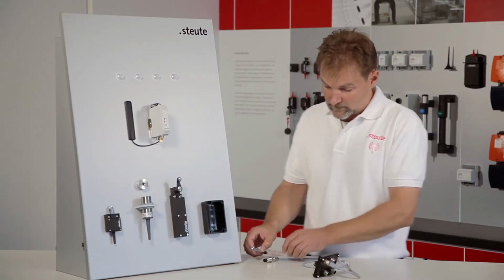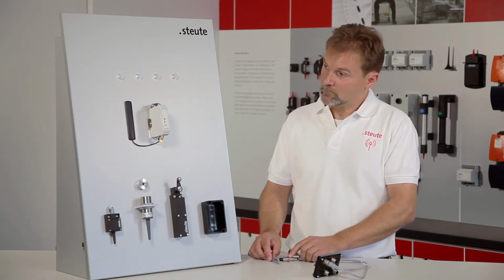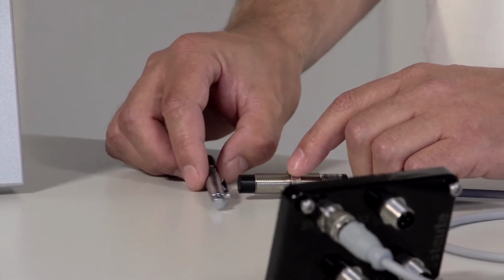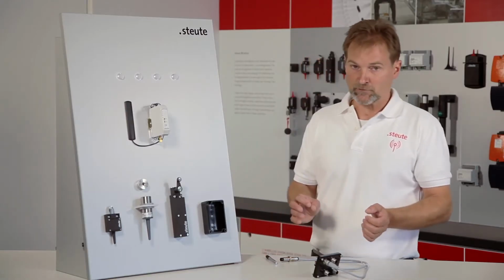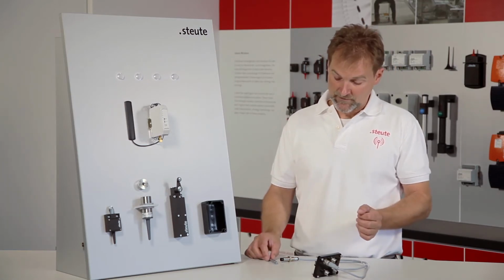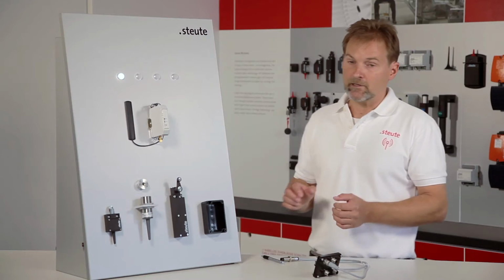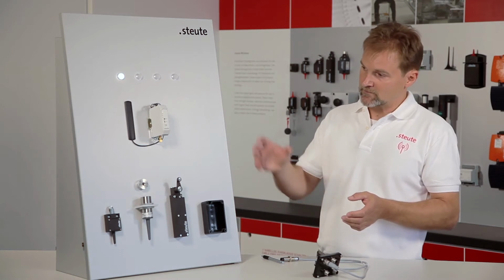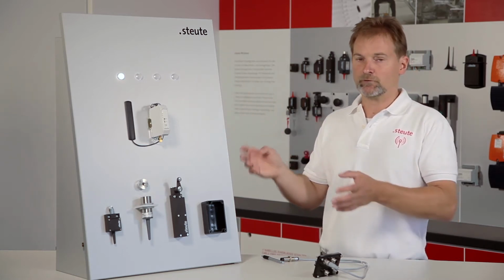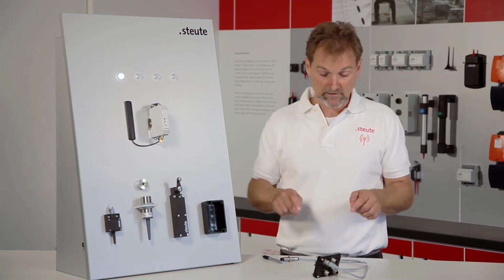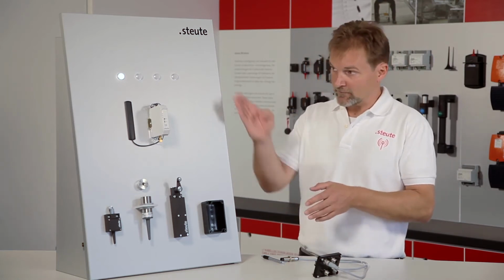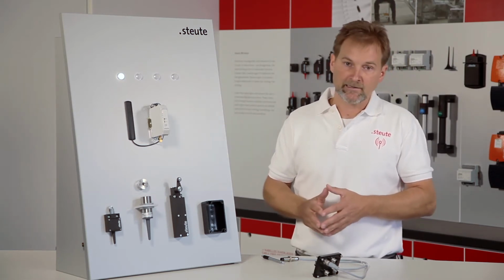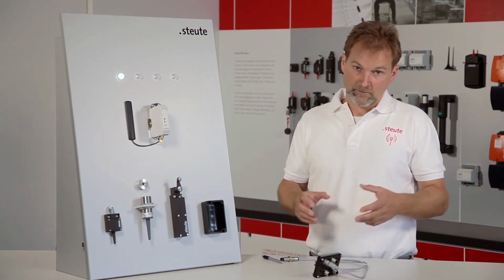I would like to demonstrate this by actuating the switch. As you can see at the top here, the switch has already undergone teaching in on the receiver and is switched on. Normally, if I had not set a status signal to repeat every 10 seconds, then if there was a power cut in the production hall, the receiver would lose its power. Afterwards it would get its power back, but it would not know that the last status of the switch was on. It would then not engage the relay, in this case relay number 1 or channel 1.